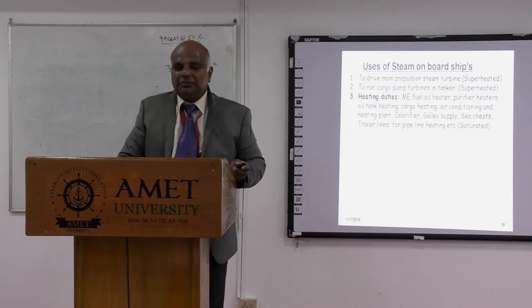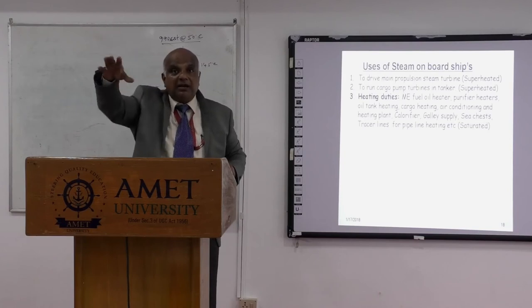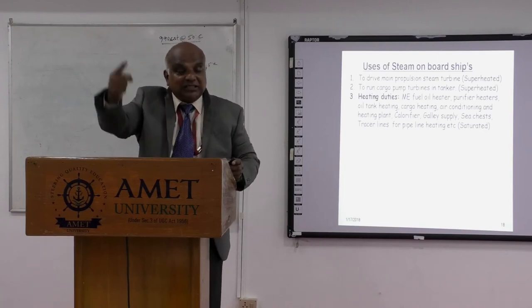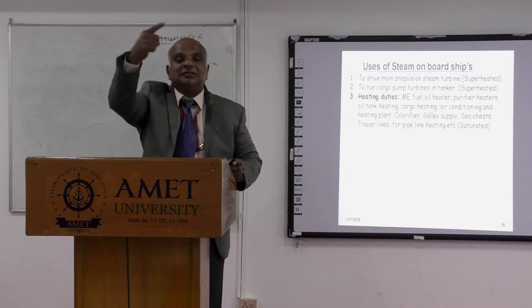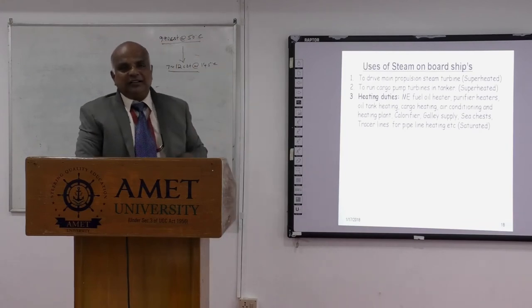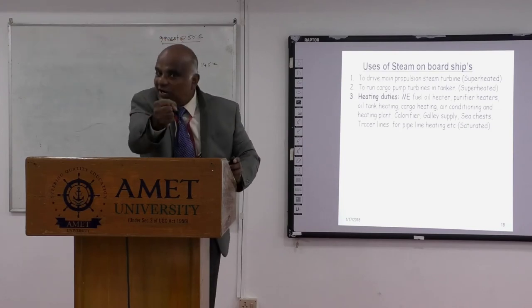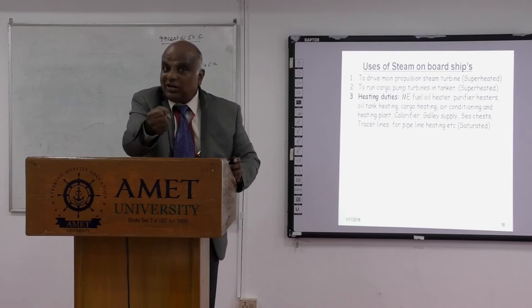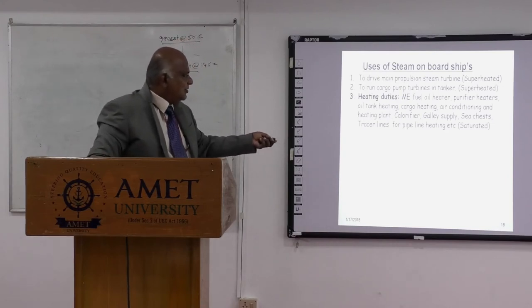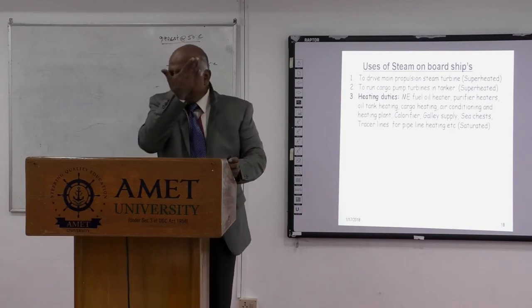Sixth, cargo heating — for example, low sulfur fuel oil cargo must be recirculated and kept warm at around 45 to 50 degrees centigrade for discharging. On long voyages, if cargo is not kept warm it solidifies and cannot be pumped out, so steam is used for cargo heating.